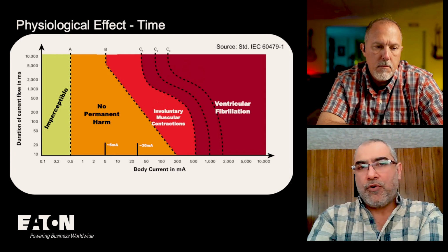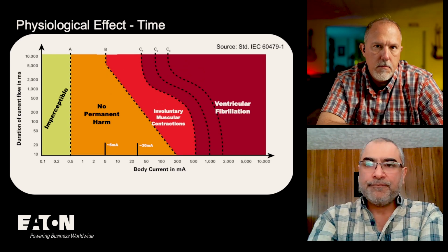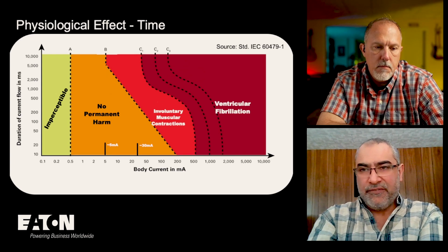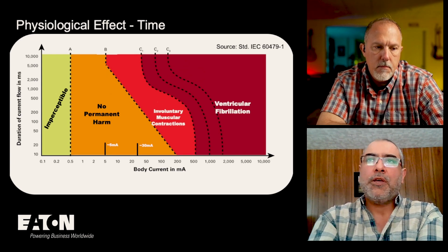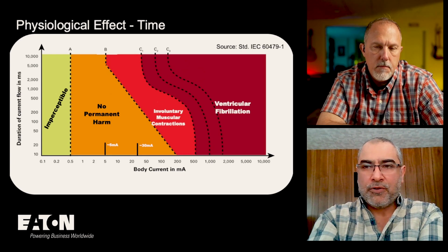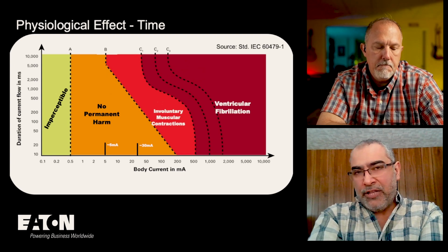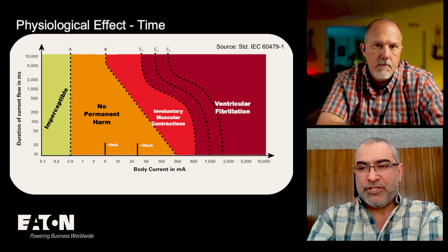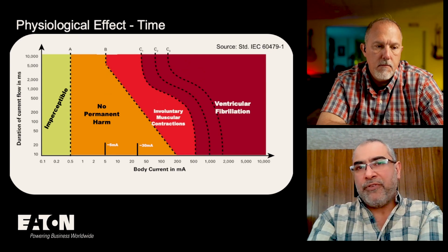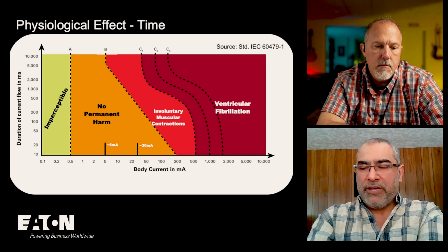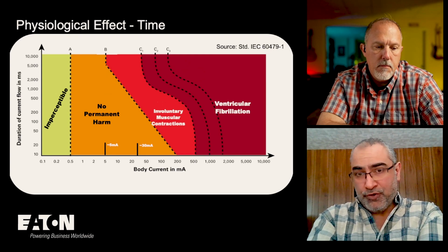So this is the difference between the two philosophies. North America provides let-go and ventricular fibrillation protection. In Europe, RCDs - the international counterpart of GFCIs - provide ventricular fibrillation protection but not let-go protection. At the end of the day, both devices are designed to trip quick enough to prevent electrocution.